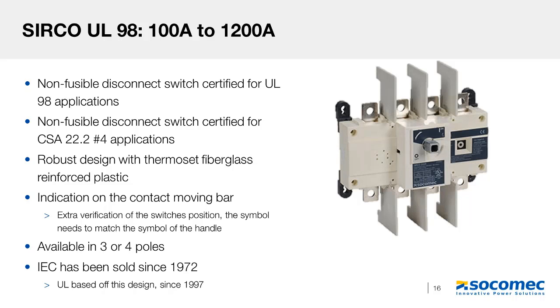And then another UL98 switch that we offer is for higher current rating UL98 applications. This switch is rated from 100 to 1200 amps. This design has been sold in the field since 1972 and has proven reliability, robustness, and quality. One of the really cool things that I like about this switch is that on the right-hand side of the switch, you can see this indication of the position of the switch. If this symbol on the right-hand side doesn't match the symbol of the handle, then you know that there's an issue with the switch. It's an extra safety precaution for people to really ensure that the position of the switch is what it's supposed to be in.